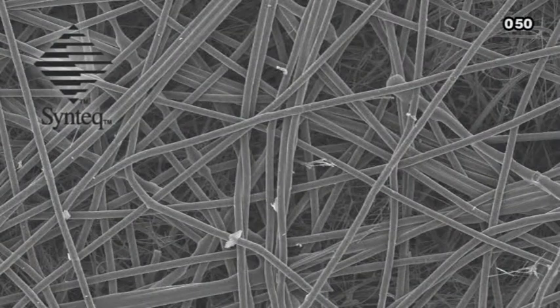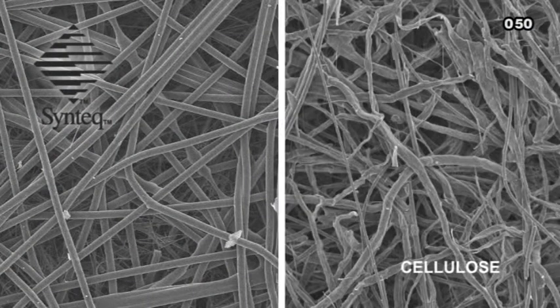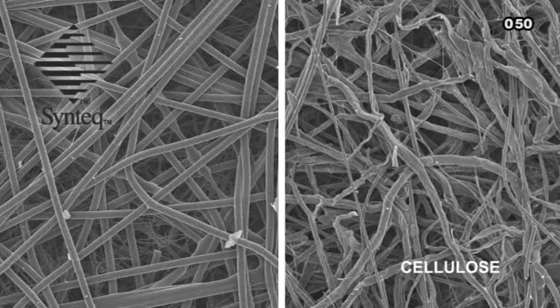Although cellulose media will suit some applications, others may require Synteq synthetic media in medium-pressure applications. For the same media area, the Synteq media gives a lower pressure drop than the cellulose media due to thinner fibers.